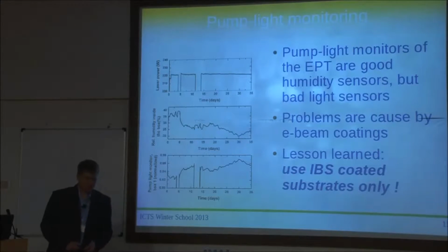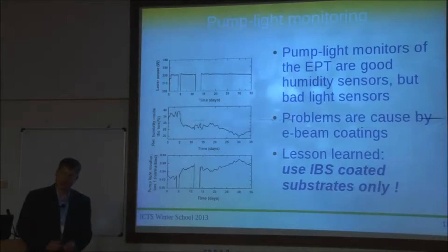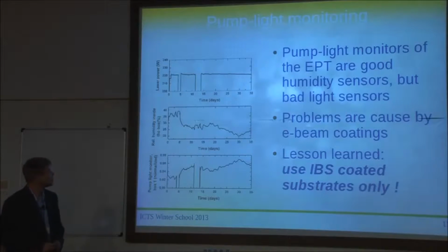So what we found for this pump light monitor at the engineering prototype, or what at least I learned, what I didn't know before, is that you want to have a special coating for actually all the components inside that laser box. But this was the part where I really learned that lesson.